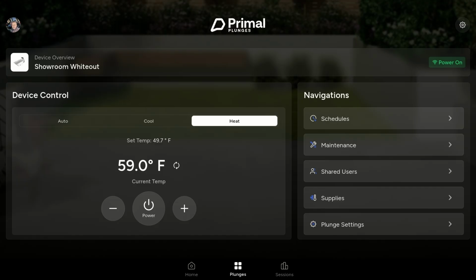Both these settings will keep the water within 2.5 degrees of your set temperature. You'll also notice an option that says auto. Auto will keep it at your set temperature plus or minus 2.5 degrees. This is useful if you're in cold environments where you may have to cool the water during the day when the sun's out, but also add heat to it at night to keep it up to temperature.